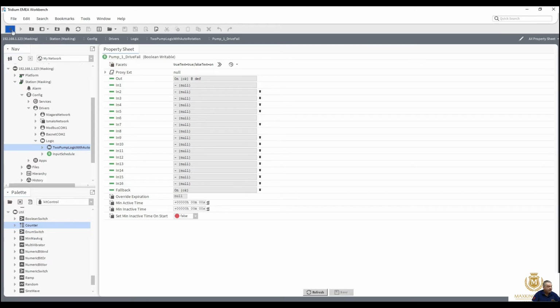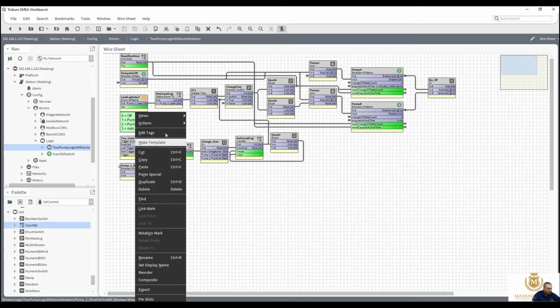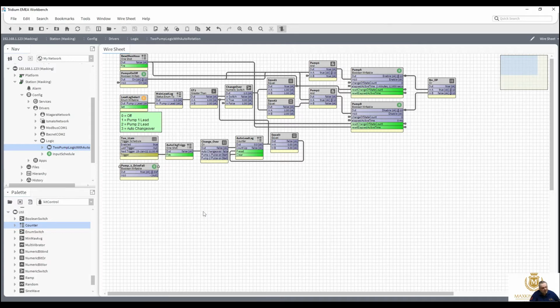So we don't know until we start commissioning, but in order to make life easier for us, we'll come to the decision that it's failed, it goes true just for the moment, but that's not fail safe. So the best way of doing it is true is healthy, but we don't know until it's wired on site.